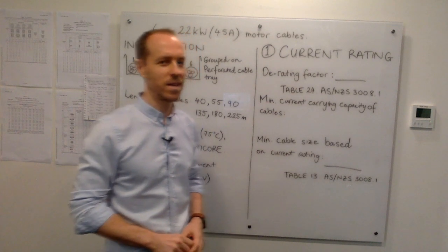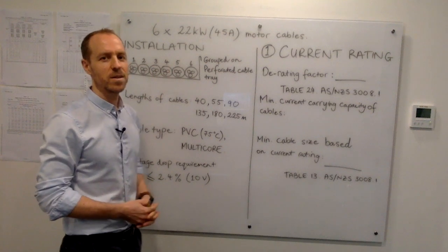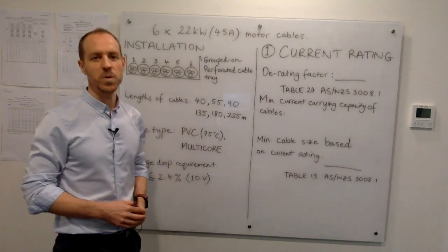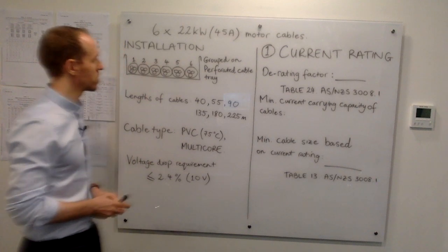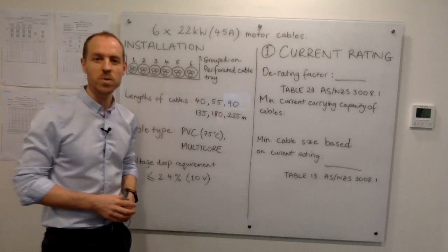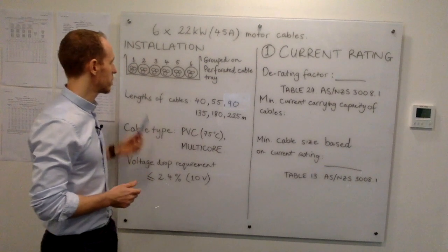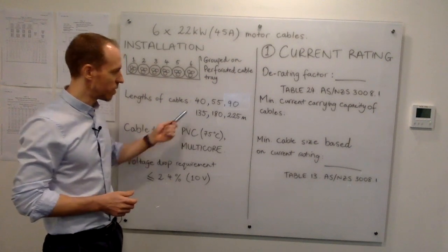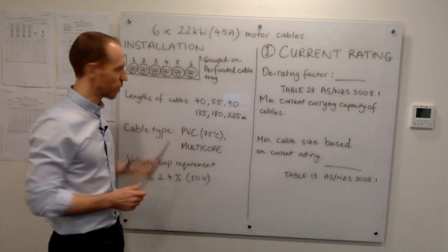Let me explain the example. We've got six 22 kilowatt motors, each requiring 45 amps per phase — so these are three-phase motors. These six cables are going to be installed on a perforated cable tray, touching. Each of the six cables goes to each of the six motors.